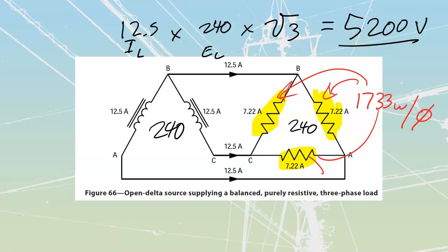What we see overall is a great reduction in the total amount. Although we know that each of these individual phases over here should be able to put out 3 kVA total, what we're actually getting out is 5,200. That's not 6,000. If I had 3,000 plus 3,000, that would get me 6,000. The actual amount that's out of here is going to be less than that, and it's just due to the fact that they are operating in this open delta configuration. The percentage that they're going to have is, depending on how you want to look at it, 2 different ways that we can take a look at it.